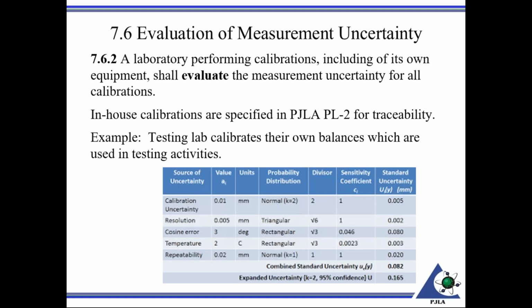A laboratory performing calibration, including of its own equipment, shall evaluate the measurement uncertainty for all calibrations. So there we're identifying different contributors, quantifying, combining, expanding. It mentions including their own calibration, and we define this in PL-2 for traceability. This would be, for example, if you're a testing lab, and we do have some labs that have in-house calibration, where we actually need to have a calibration assessor witness those to assure traceability. So part of traceability would be the uncertainty. So if you're doing in-house calibrations, bear in mind you have to evaluate the uncertainty of those if it's needed for traceability, and 7.6.2 would apply.